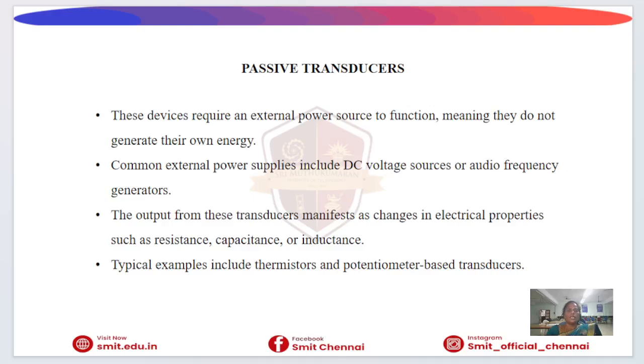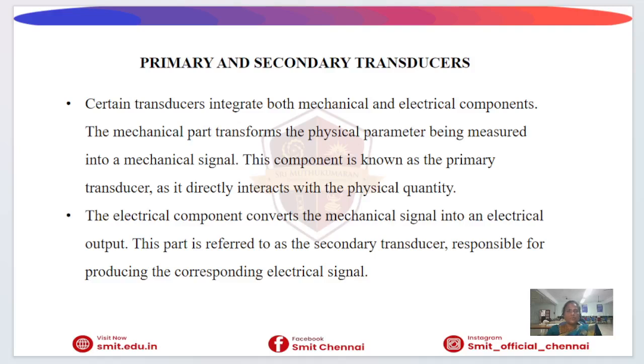Passive transducers require an external excitation or power source to operate. They function by changing electrical properties such as resistance, capacitance, or inductance in response to the measured quantity. Examples include thermistors, strain gauges, potentiometers, and LVDTs. Since they depend on external power, the measuring circuit detects changes in their electrical characteristics and converts them into a useful output signal.